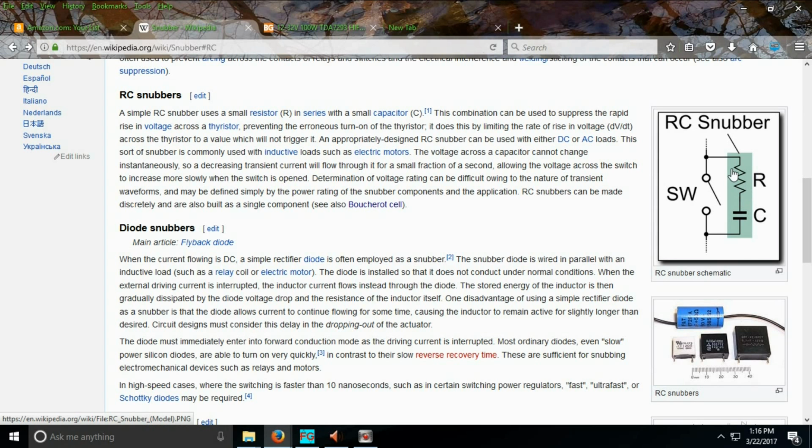So often you're supposed to really derate a relay contact. If you're using it right at its max and you're going to put a diode across it, it's not going to work. You're going to end up burning up your contacts because they won't release smooth, and you get a nice fast sharp release off of a relay without any kind of snubber on it or switch. Once you put a snubber across a switch, that energy's got a path.